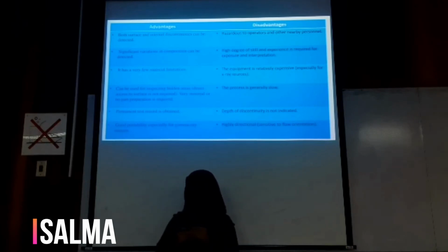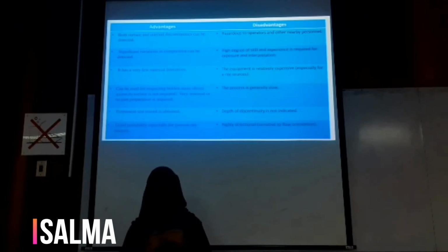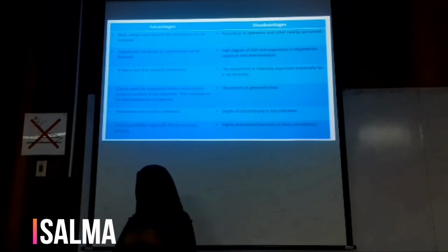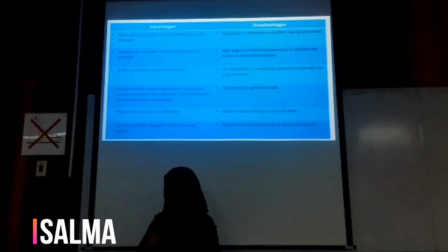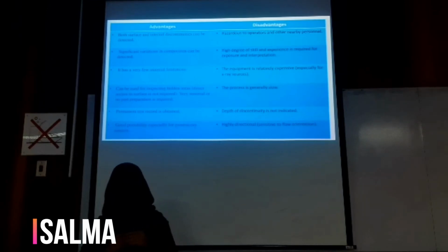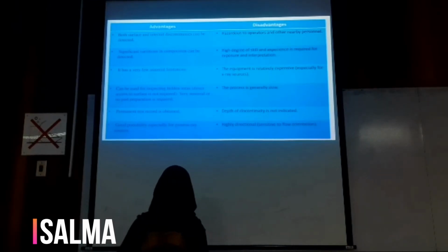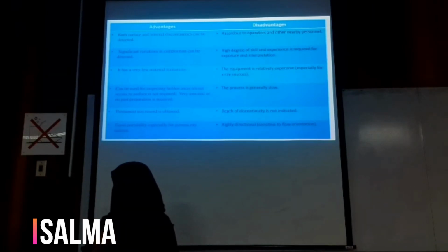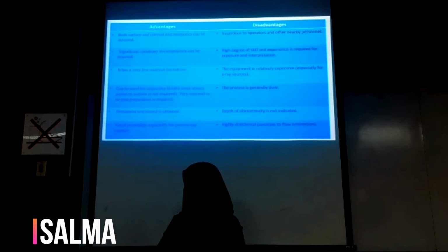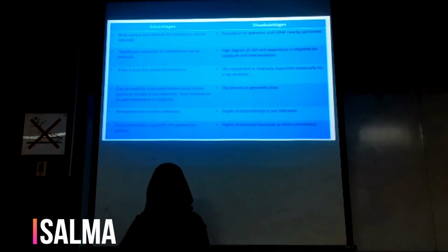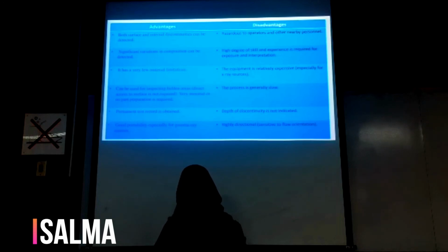The second disadvantage is that it requires very high skill and also experience for the worker to deal with this method or apply this test. It also requires very expensive equipment in order to carry out this test. The procedure is very slow, and in the image it cannot detect the depth of the discontinuity. It also needs high directionality in order to detect the crack. For example, if the X-ray is not parallel to the crack, it will not be seen.